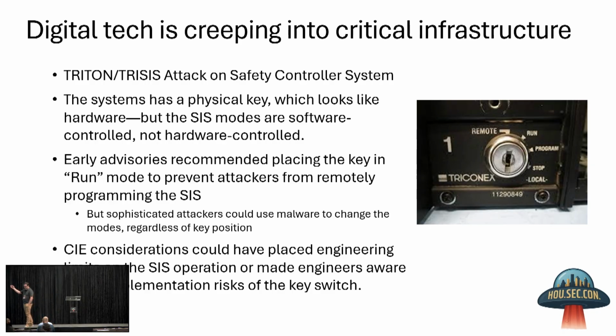A perfect example was the Triton attack at Aramco, where they compromised that safety instrumented system by getting inside the memory of that controller and allowing them to overwrite and rewrite, to their heart's content, what was the expected operation. From a safety perspective, that's a complete loss of that safety objective. You have no guarantees because of their ability to manipulate that memory within the safety instrumented system.